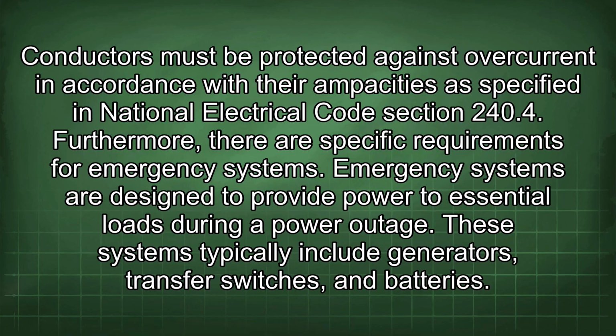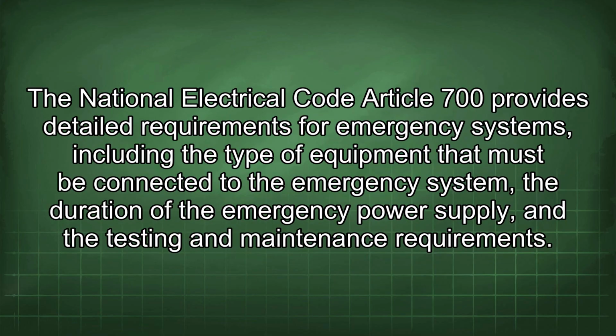Furthermore, there are specific requirements for emergency systems. Emergency systems are designed to provide power to essential loads during a power outage. These systems typically include generators, transfer switches, and batteries. The National Electrical Code Article 700 provides detailed requirements for emergency systems, including the type of equipment that must be connected to the emergency system, the duration of the emergency power supply, and the testing and maintenance requirements.